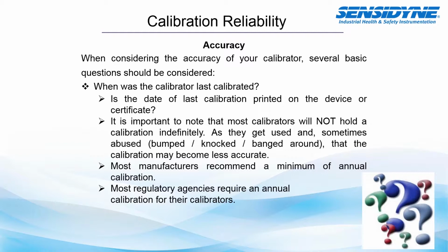So it's important that when you send your calibrators back, you follow your manufacturer's recommendations. At Sensidyne, we recommend that calibrators are calibrated annually. I can tell you that most regulatory agencies also require annual calibration for their calibrators. Minimum is usually an annual. Some companies may actually prefer more than annual calibrations take place.